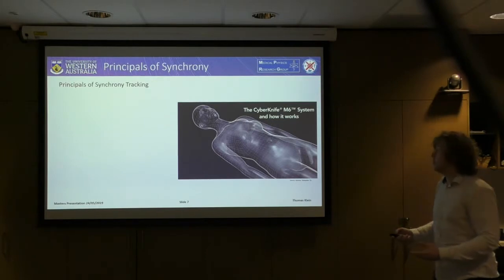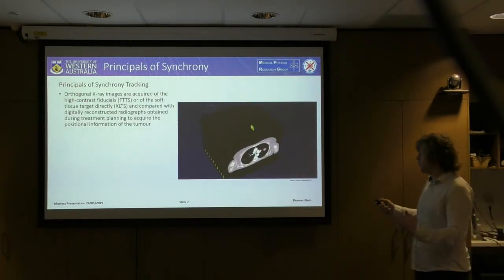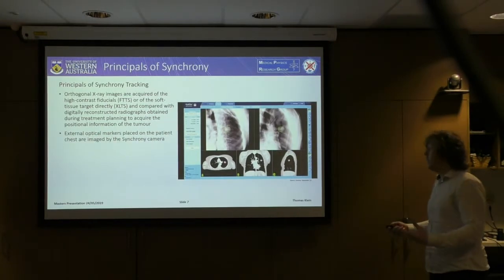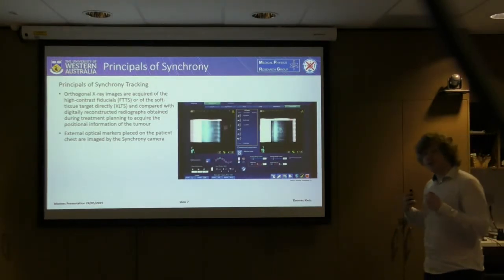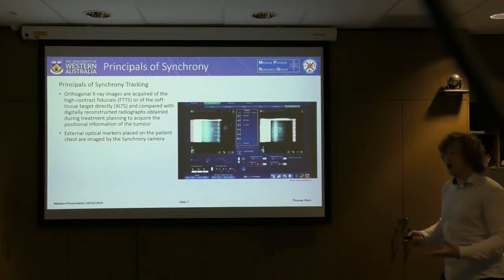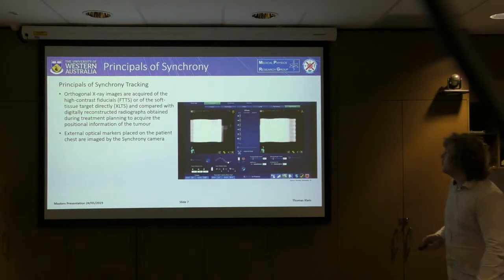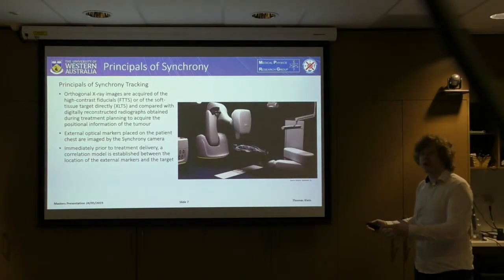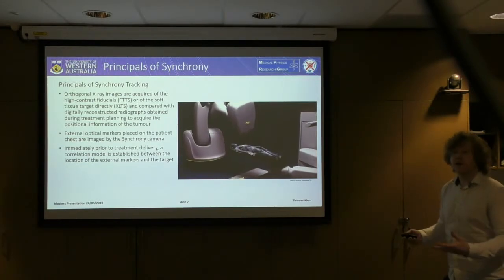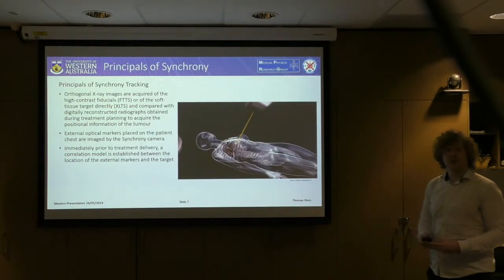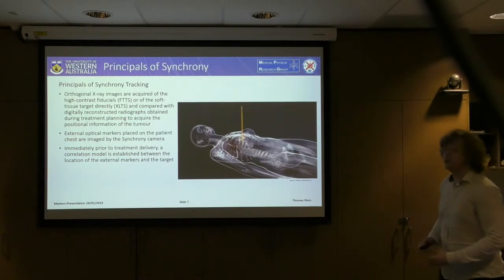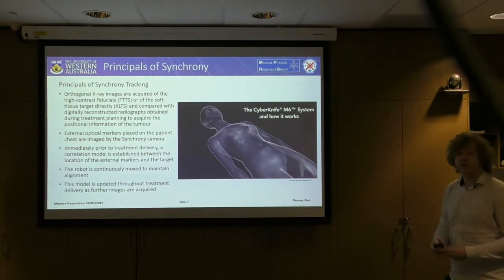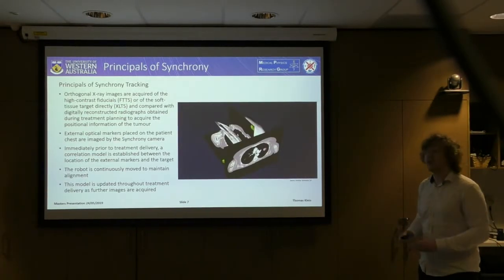Briefly covering the basic principles of Synchrony tracking: orthogonal x-ray images are acquired of either the fiducials or the target directly, and compared to the CT dataset to acquire the positional information of the tumour. Simultaneously, external optical markers placed on the patient's chest are tracked by the Synchrony camera. By acquiring images in conjunction with tracking the patient's chest, a correlation model is established relating chest position to target position. The robot is continuously moved to maintain alignment, and images are updated approximately every 30 seconds to account for changes in real patient respiration.